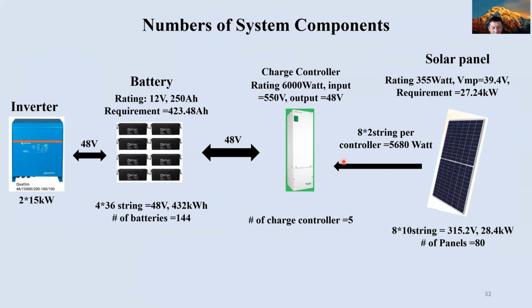Now focus on the number of components. Our total load is about 31 kilowatt, which is not peak, so we select 2 inverters of 15 kilowatt each. For the battery, our requirement was 423.48 ampere hour, and the battery we selected was 12 volt 250 ampere hour. But the voltage rating of the inverter is 48 volt, so we have to connect 4 batteries in series to make the 48 volt and to cover 423.48 ampere hour, we have to make 36 strings. So in total, the capacity of the battery is 432 kilowatt hour and the number of batteries is 144.